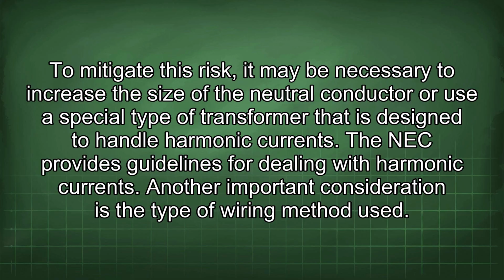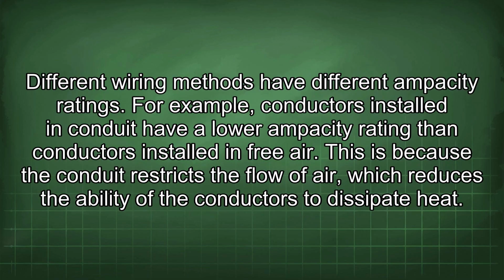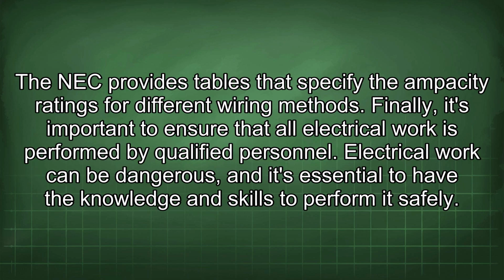The NEC provides guidelines for dealing with harmonic currents. Another important consideration is the type of wiring method used. Different wiring methods have different ampacity ratings. For example, conductors installed in conduit have a lower ampacity rating than conductors installed in free air. This is because the conduit restricts the flow of air, which reduces the ability of the conductors to dissipate heat. The NEC provides tables that specify the ampacity ratings for different wiring methods.